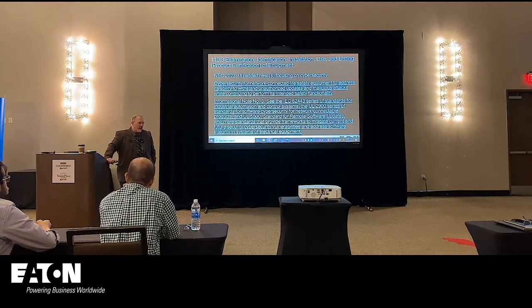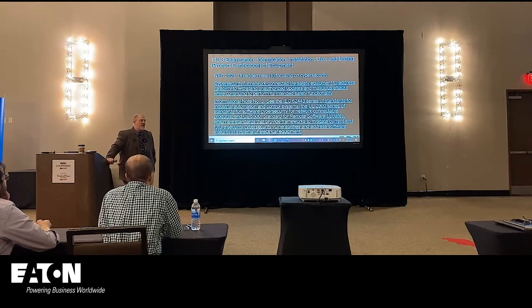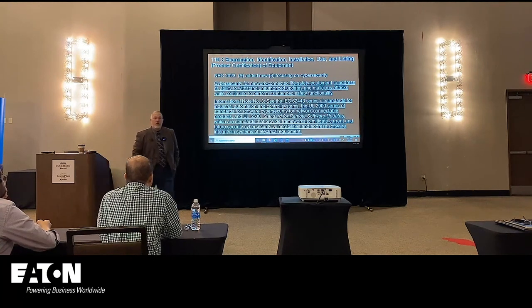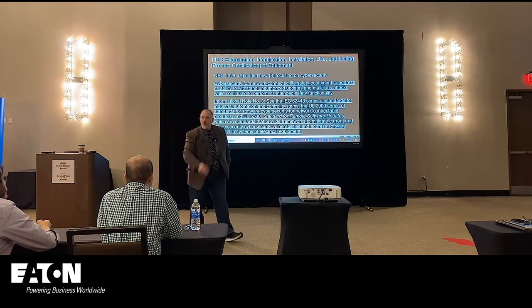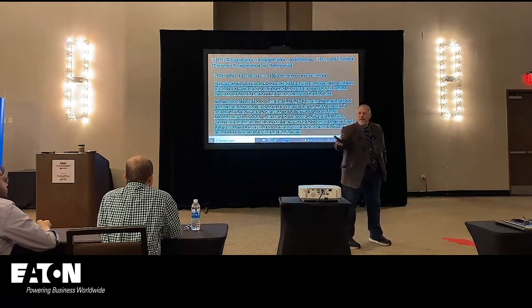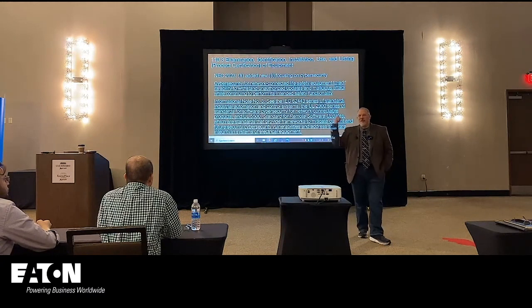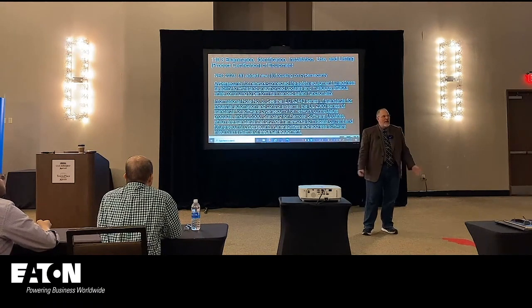This is what an electrical inspector is supposed to review your installation in regard to, right? Which is very, very vague. Okay, what is a life safety system? If you would assume a life safety system would be what? Article 700, right? I would go back to 700. There are no requirements in Article 700 that were accepted by Panel 13 around cybersecurity. So you say, well, I don't have any requirements there.